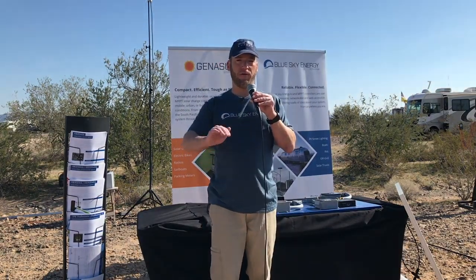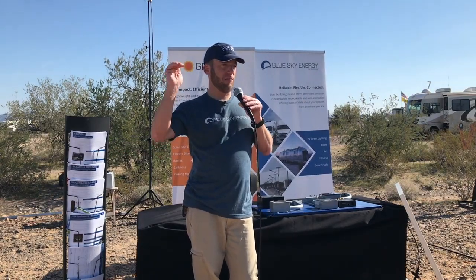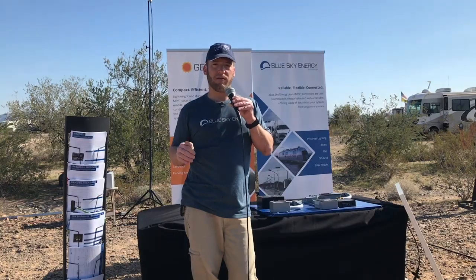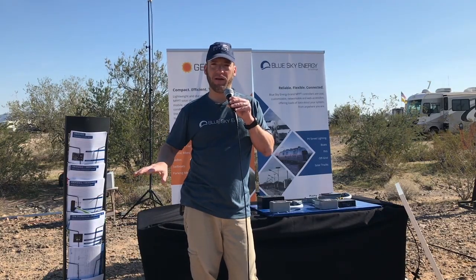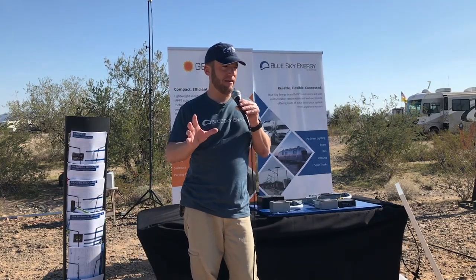Because our controllers are so programmable, you can tell the controller to hold the float voltage forever, but every 2 or 3 weeks go to the absorption voltage for a couple hours, just to make sure those batteries stay completely desulfated. It's just a bunch of settings, and it's a really easy thing to do.